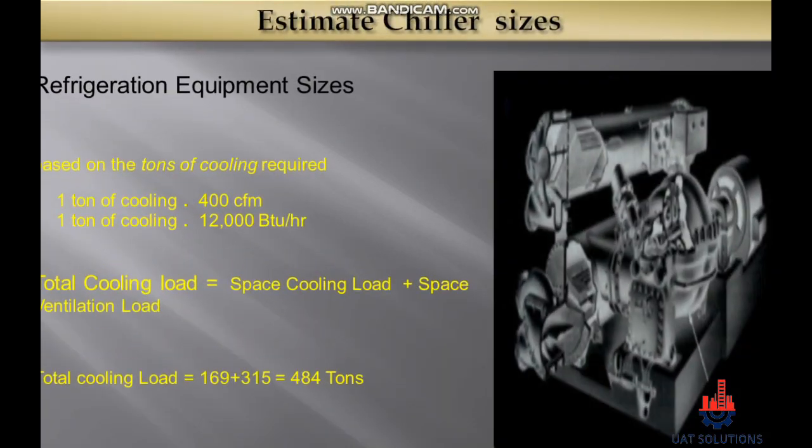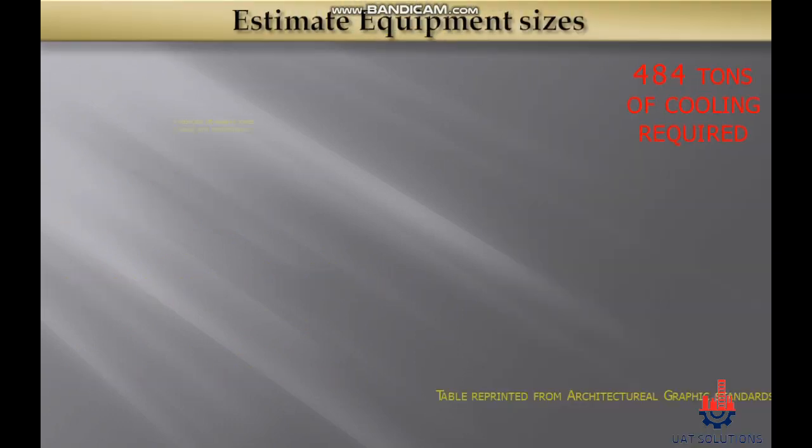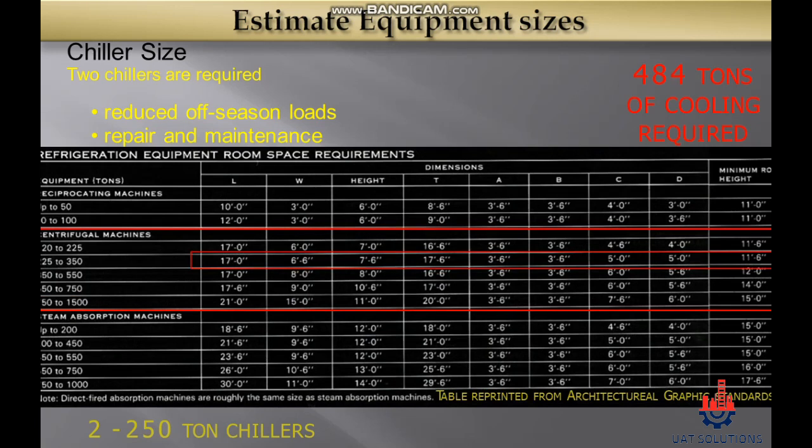The final step is to combine space cooling load and ventilation cooling load: 169 tons for space cooling plus 315 tons for ventilation cooling equals a total refrigeration system requirement of 484 tons. The chiller size and cooling capacity can be selected using the shown table.